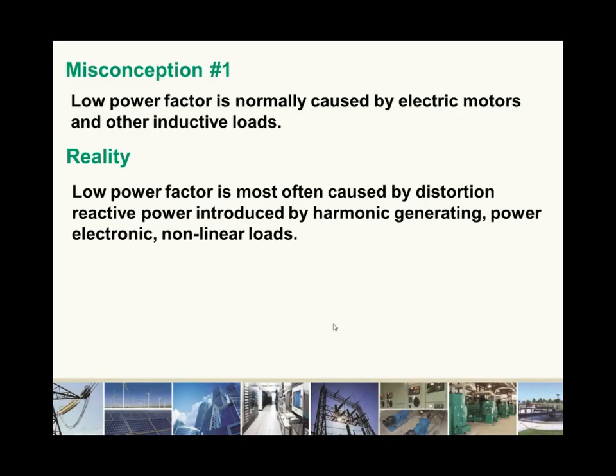So the first misconception is that low power factor is normally caused by electric motors and other inductive loads, when in reality, low power factor is most often caused by distortion reactive power introduced by harmonic generating power electronic nonlinear loads.